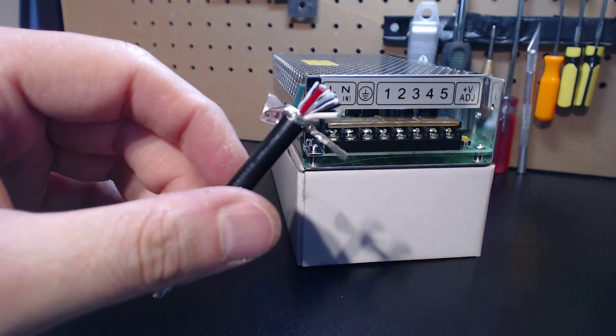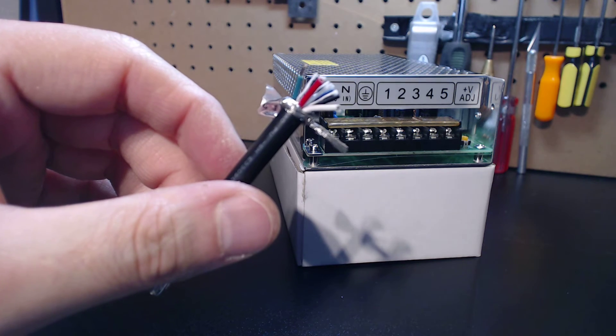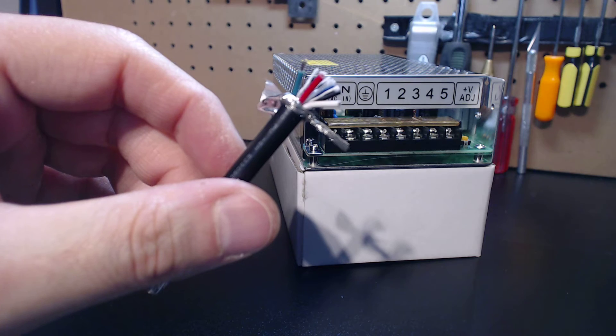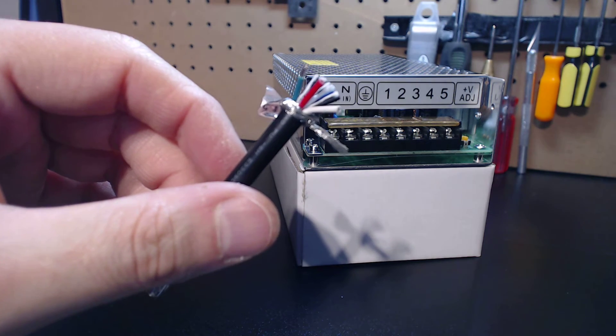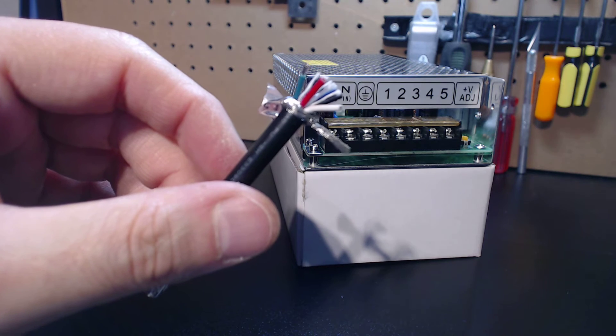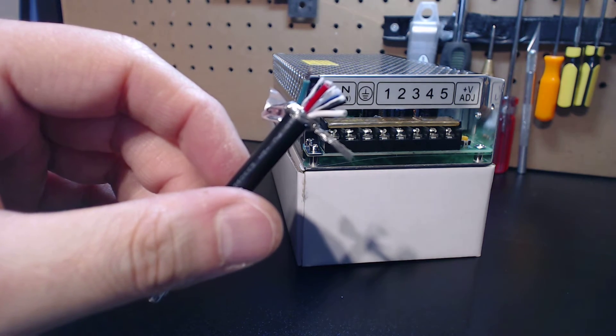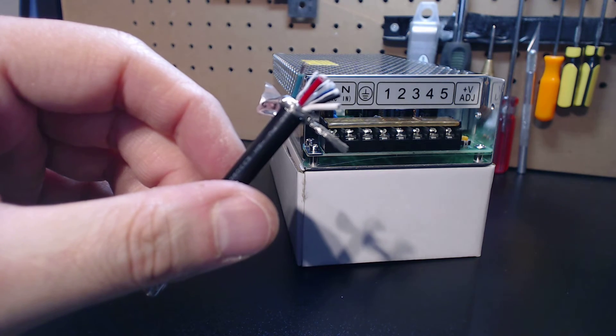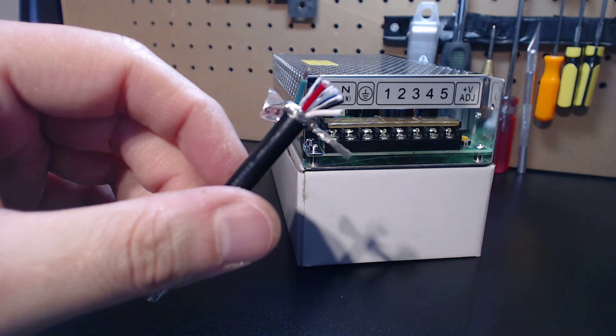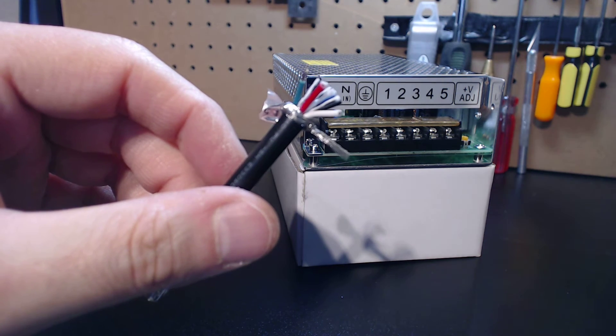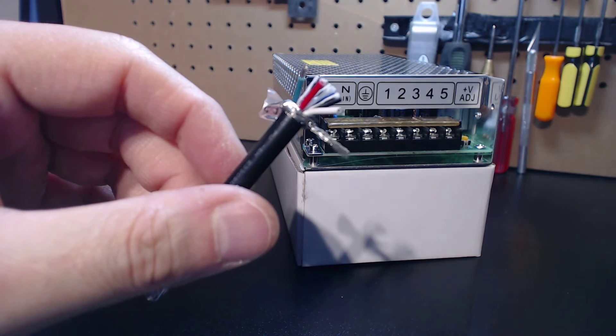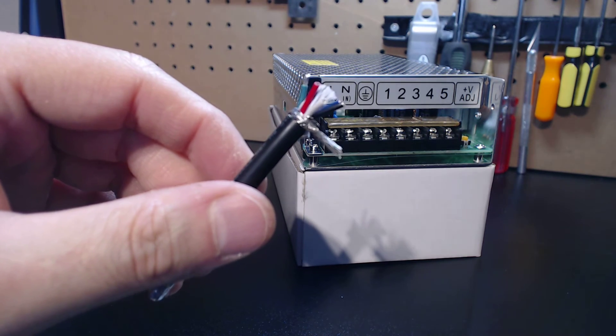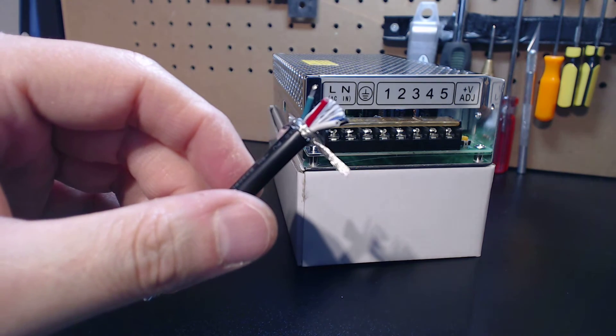When I see guys using crimp connectors on grounds, all I keep thinking of is how much resistance they're creating. You don't use crimp connectors with CNC. I've said this numerous times. Other manufacturers do it - I highly recommend against it. You're not using one crimp connector, you're using multiple crimp connectors, which means every crimp connector you put in your system you're building up resistance, and resistance yields higher EMI susceptibility. When we're dealing with precision electronics, take into account it's no different than if you were building an EKG machine. You'd want it to be as precise as possible.